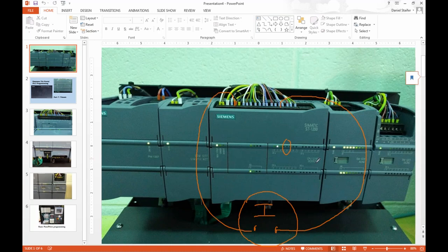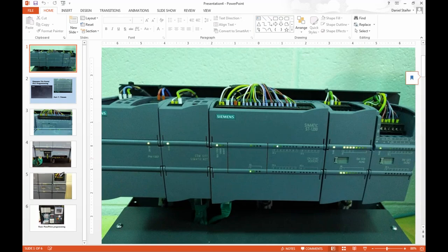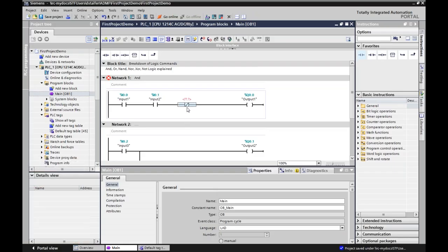The hardest thing for electricians is getting off the mindset that if you have a normally closed contact, the input is on, and programming accordingly. All the contact symbol is saying is: is the input high? If it is, return true and allow logic to pass. The normally closed symbol asks: is the input false or low? And if so, return true. You can ask the same question four different ways to get a different true or false answer.